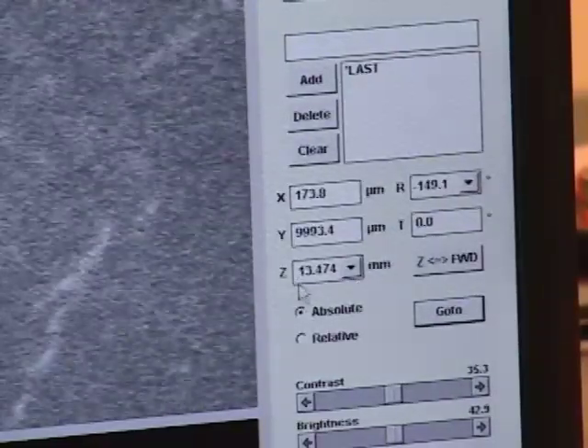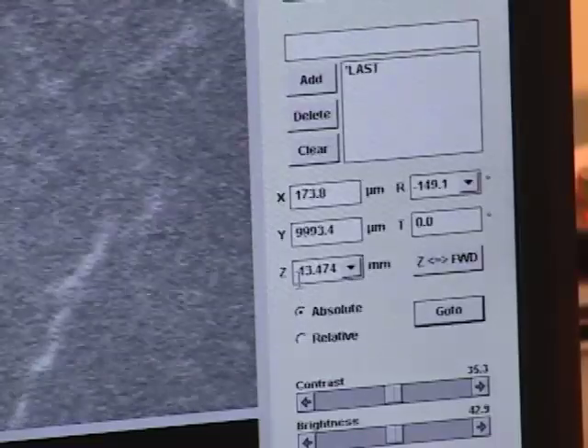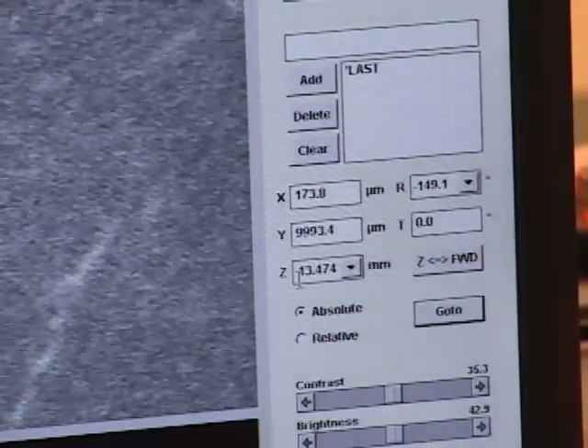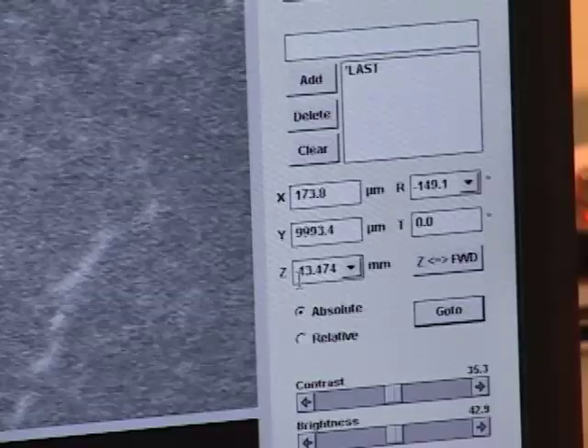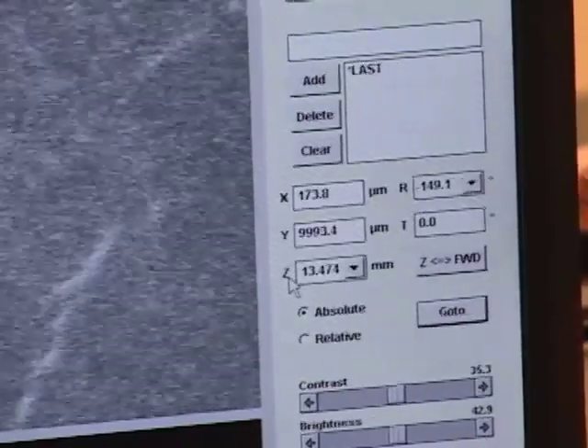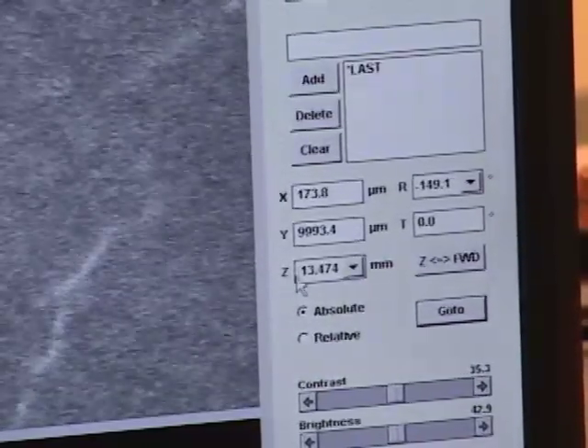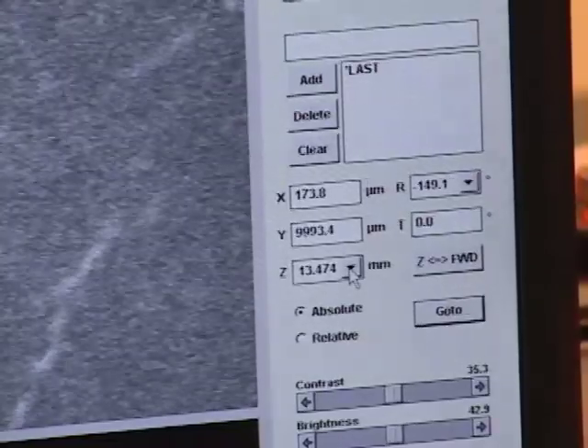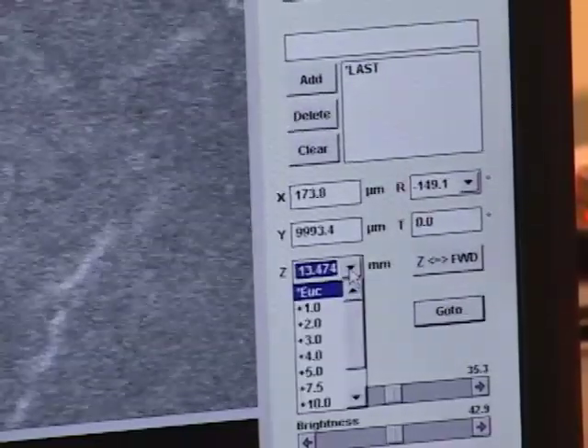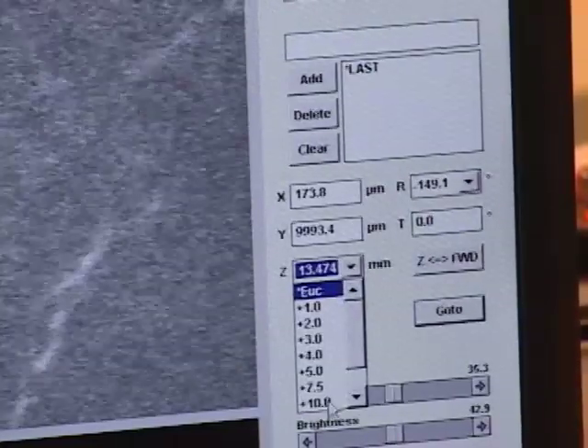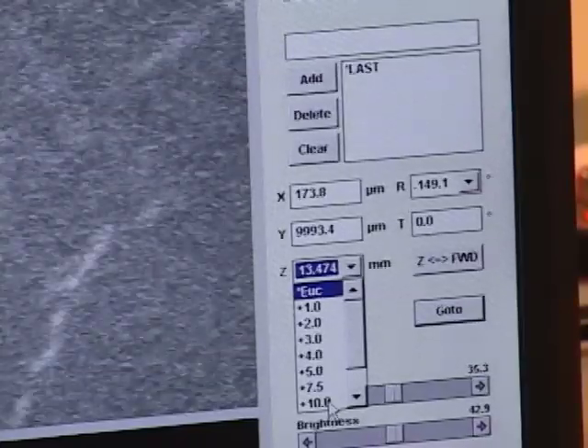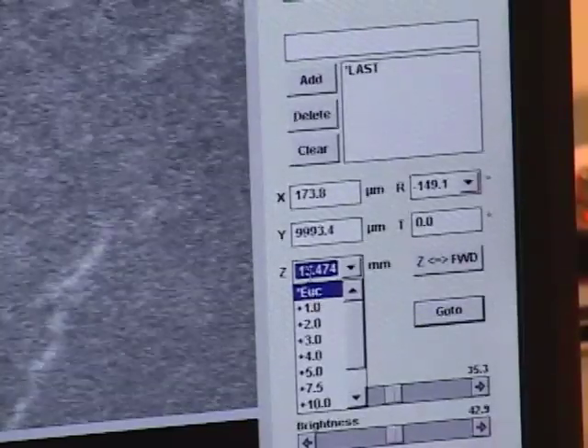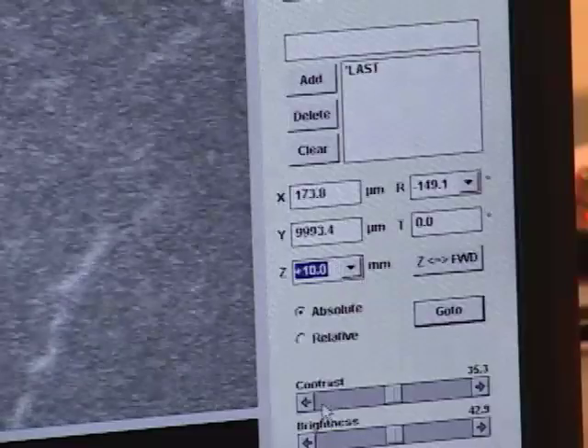Ultimately, I want to do my imaging at about 5 millimeters working distance. As a safety measure, I'm going to reduce this to 10 millimeters first, recalibrate the stage height, and then move to 5 millimeters. So to adjust the stage height, I click on the drop down menu in the Z field and I select the final clearance that I want from the detector. Right now we're going from 13.4 to 10 millimeters.